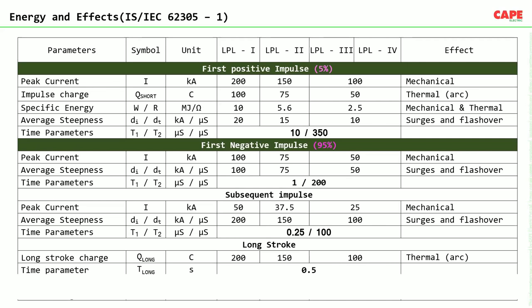First, we'll talk about the first positive impulse. That means the impulse which is generated due to a positive lightning strike. Now, this is very rare, generally accounting for 5% of the total lightning strikes. In the first positive impulse, peak current will be around 200 kiloamperes in level 1. We all know that there are four lightning protection levels: level 1, level 2, level 3, and level 4. In level 1, first positive impulse will have 200 kiloamperes current. In level 2, it will have 150 kiloamperes of current. Level 3 and 4, it will have 100 kiloamperes of current.